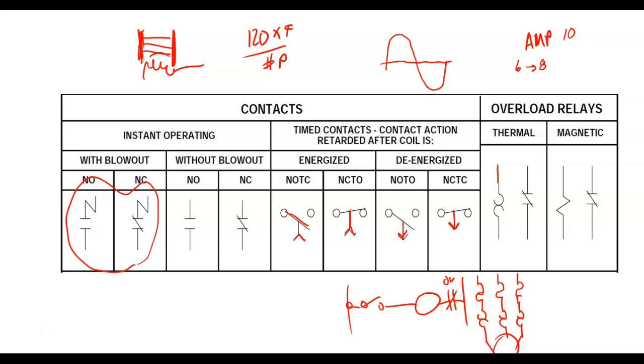So just about all your big motors are going to have overloads. Even small motors have overloads on them. A lot of them are internal. If we were over in the motor control lab, I could show you an internal overload. Most of the overloads on the motors in your house are going to be internal. Sometimes they'll have a little reset button on them where you can reset the overload, but most of the time they're thermal overloads. They use a bimetallic strip, and when they cool down, they automatically reset.